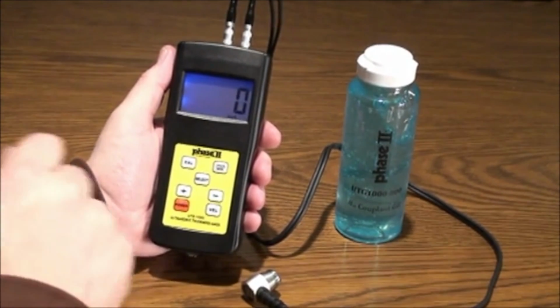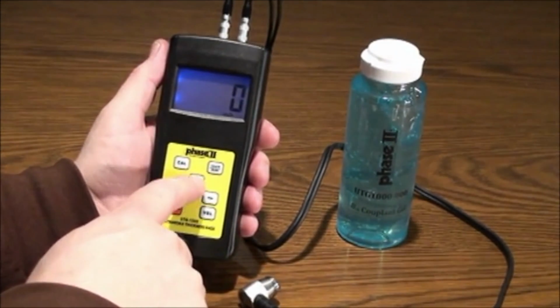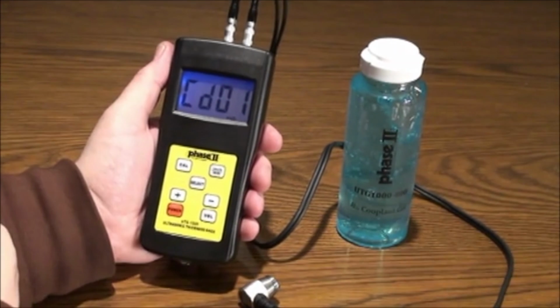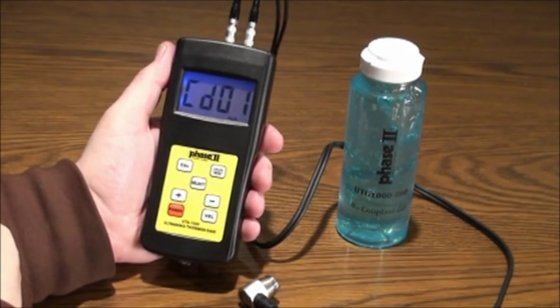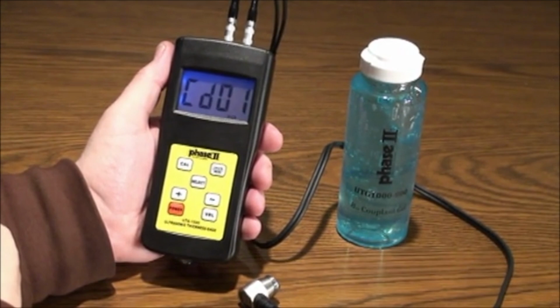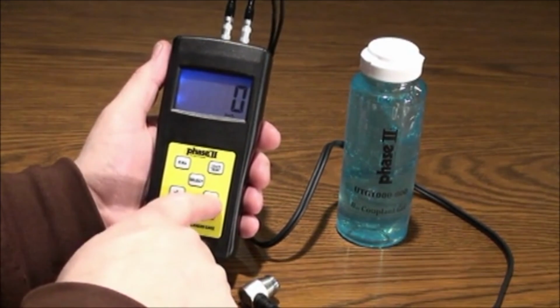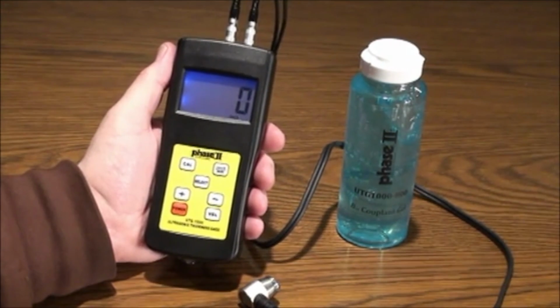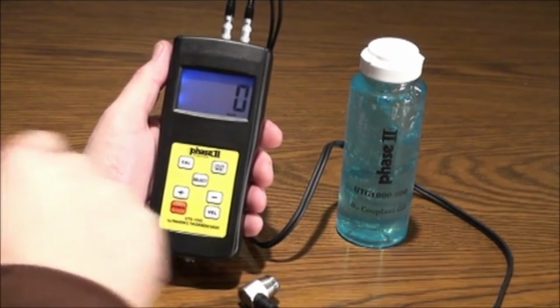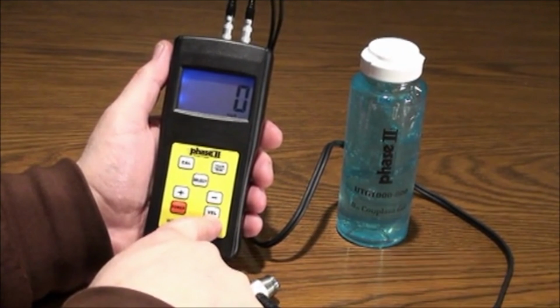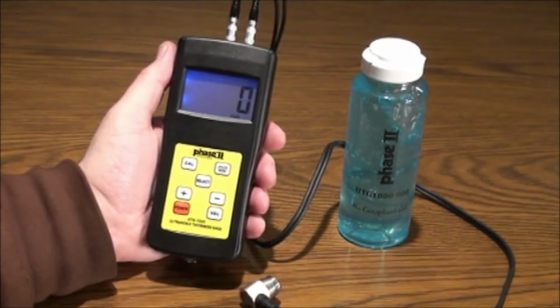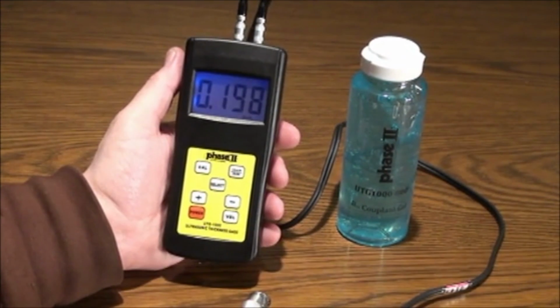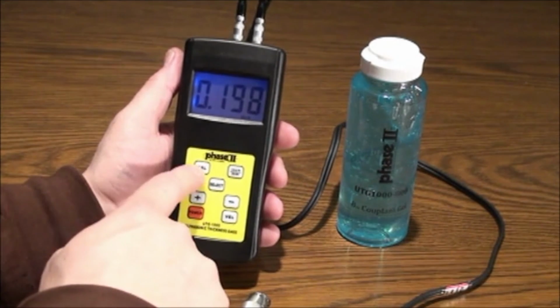The select button in the center of the keypad allows you to select the material to be tested, either for automatic velocity setting or for manual setting in code 12. Use the plus or minus arrow buttons to scroll up or down in the menu. The velocity button will allow you to enter the velocity setting during a manual setup. The Cal key is for calibration.